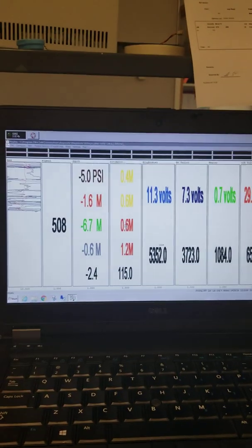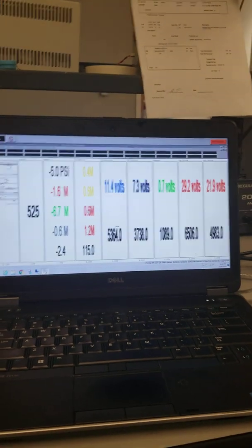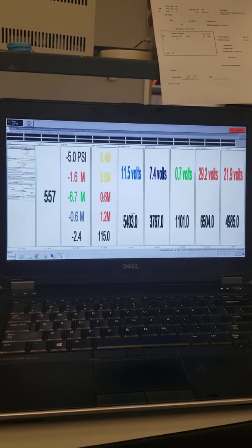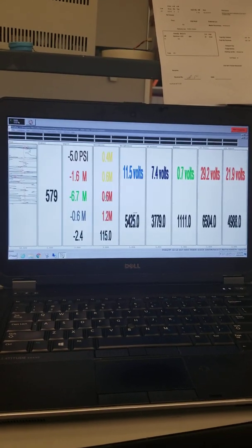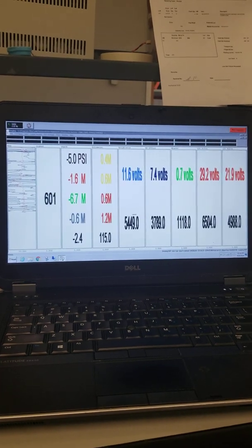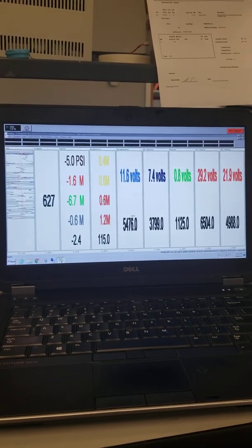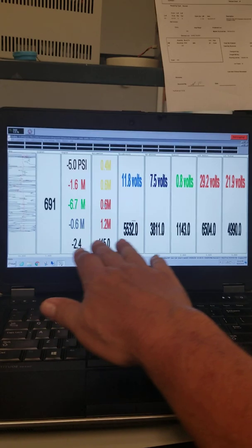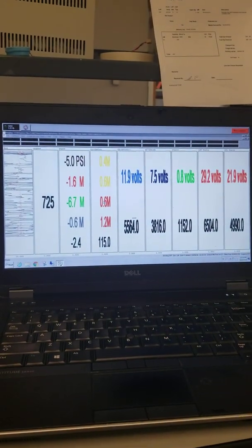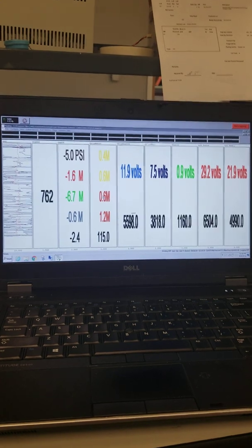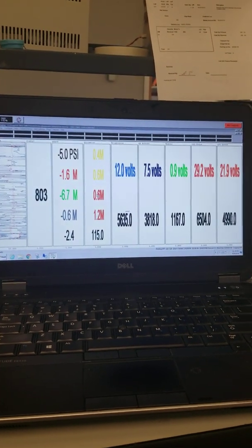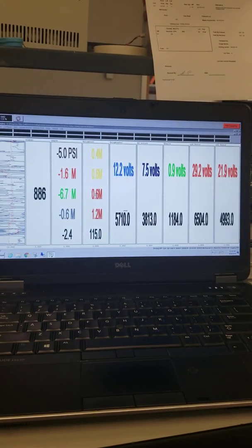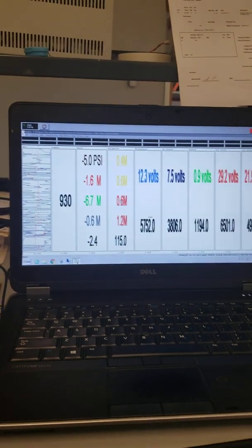Okay, so let me back off a little bit so you can see the full screen. In the diagnostic survey file, the instrument turns on all the channels, and if you look at the document that I'll send to you if you don't have it already, or it's in the manual, you'll see what's allowable numbers here. After 15 minutes or so, the instrument stabilizes, and you should get numbers that follow within the parameters set in that document, okay?